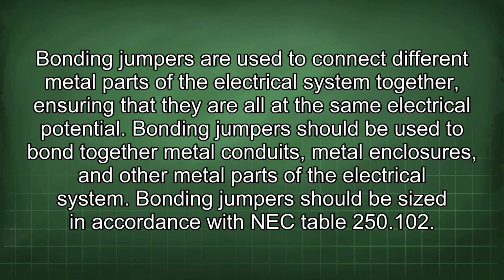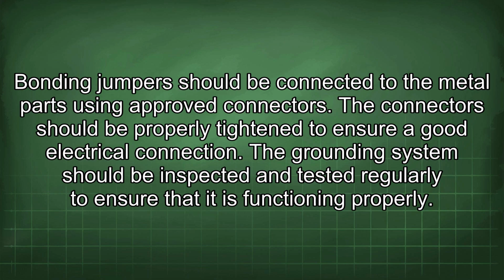Bonding jumpers are used to connect different metal parts of the electrical system together, ensuring that they are all at the same electrical potential. Bonding jumpers should be used to bond together metal conduits, metal enclosures, and other metal parts of the electrical system. Bonding jumpers should be sized in accordance with NEC Table 250.102. Bonding jumpers should be connected to the metal parts using approved connectors. The connectors should be properly tightened to ensure a good electrical connection.